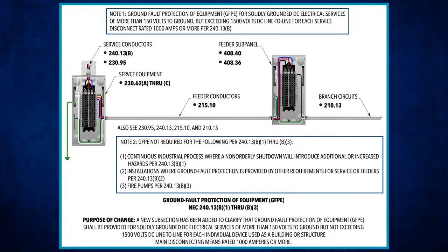What we got into there was the same requirement as a Y system: if you're providing it upstream, you don't need it downstream. So they tied all this together, where you've got 240.13 A and B, then 230.95 and 215.13 - or is it 18, I can't remember, they move stuff around so much - but the way they set this up ties in the overcurrent protection device requirements with what's required for feeders and overcurrent protection devices for services, as it pertains to ground fault protection of equipment.